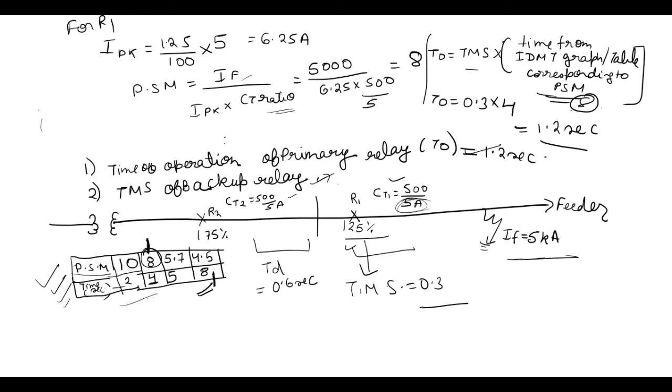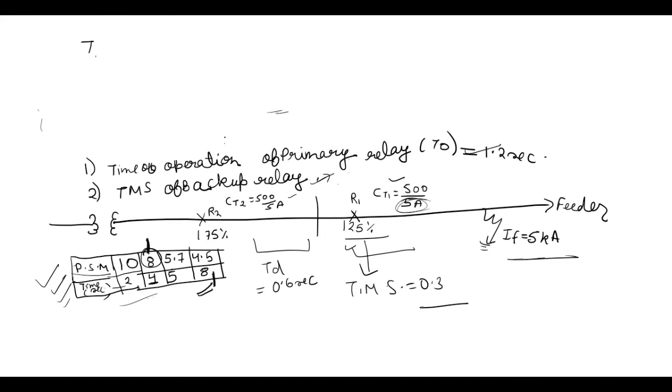And now we have to find TMS of backup relay. Okay. So we know that the time of operation of backup relay is equal to time of operation of primary relay T0 plus the delay, which is 1.2 plus 0.6, so 1.8 seconds. And now again we will find pickup current and now this is for R2.